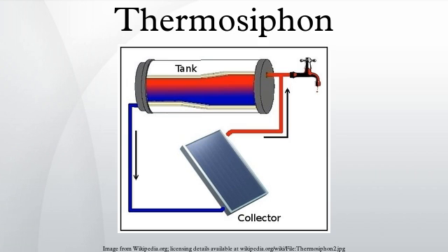Single-phase thermosiphons can only transfer heat upward, or away from the acceleration vector. Thus, orientation is much more important for thermosiphons than for heat pipes. Also, thermosiphons can fail because of a bubble in the loop, and require a circulating loop of pipes.